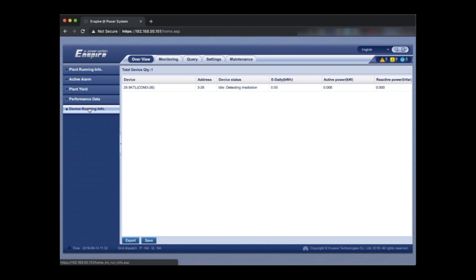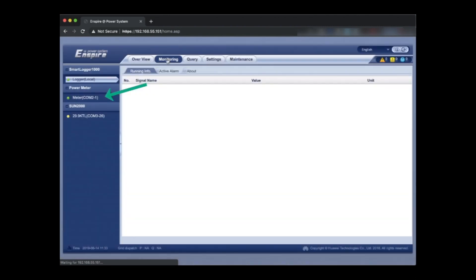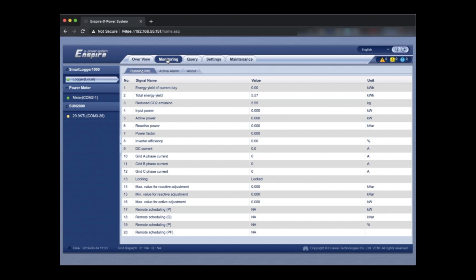So here we can see the plant and we're going to monitoring and we've got the meter on the left. It's just loading and the inverter below it. And if there is a green button next to it that means it's receiving data. So there you go. The green light on the COM interface number two has got a green light which means it's reading data from the meter and you should be able to see things like kilowatt hours etc.